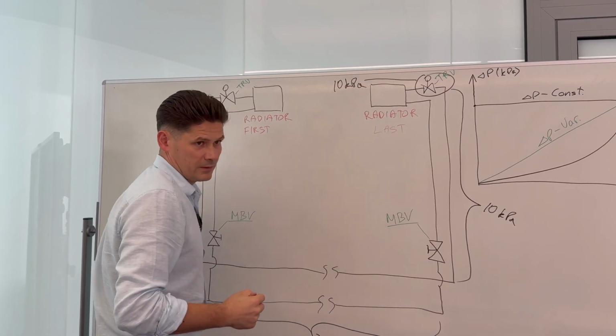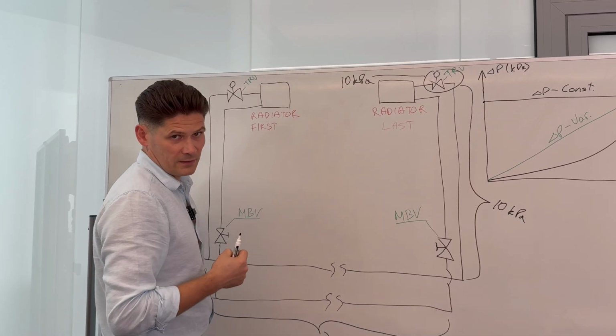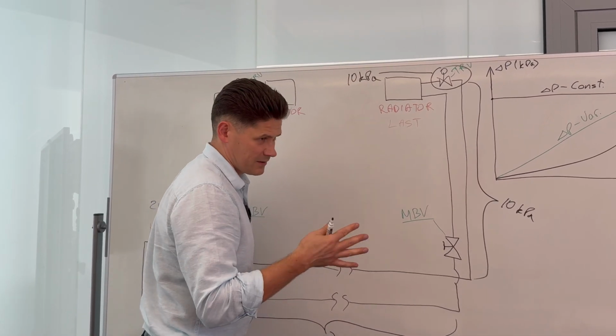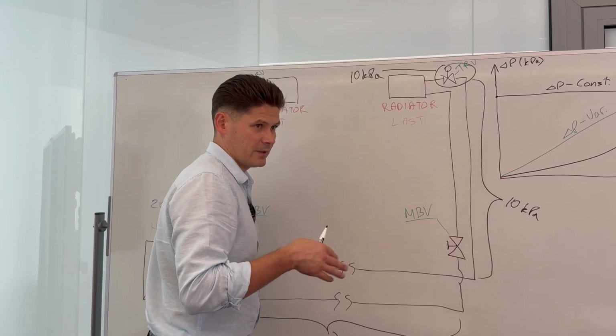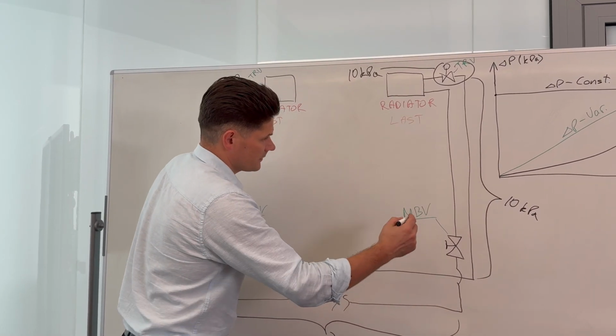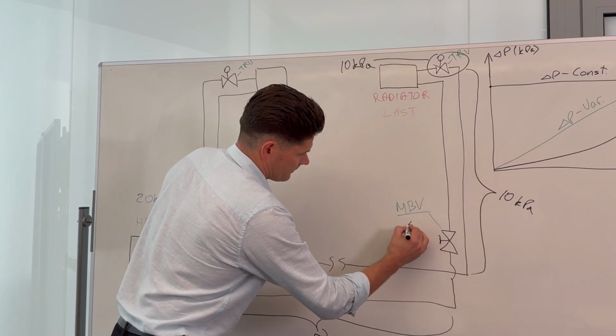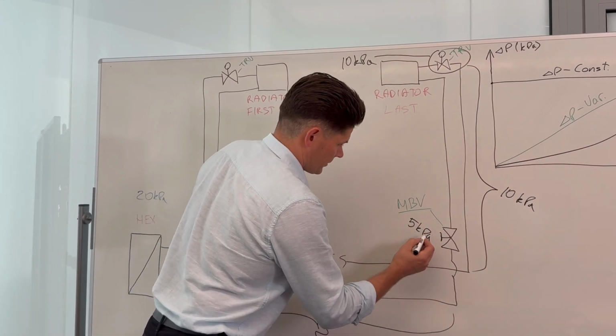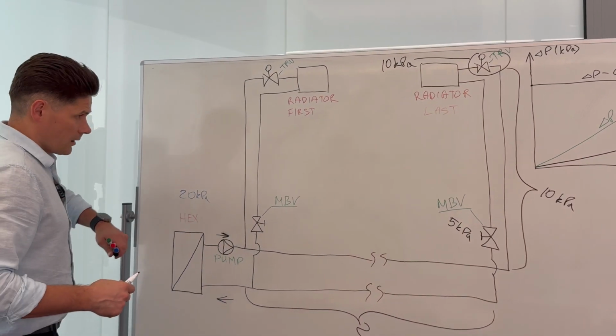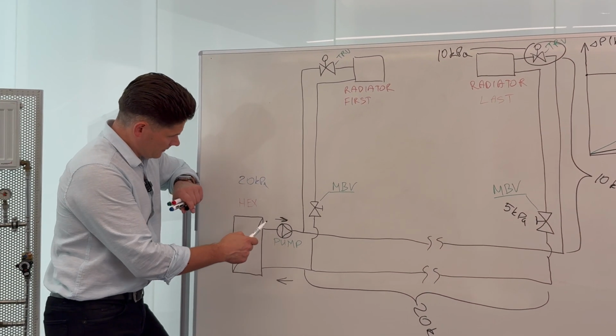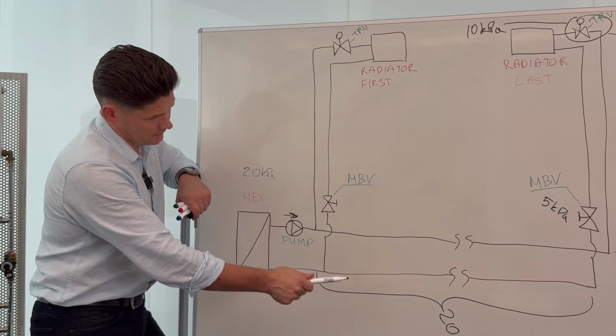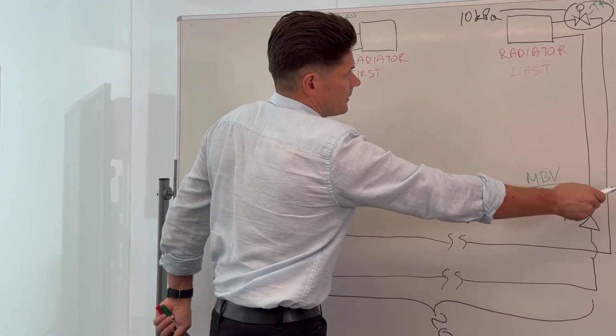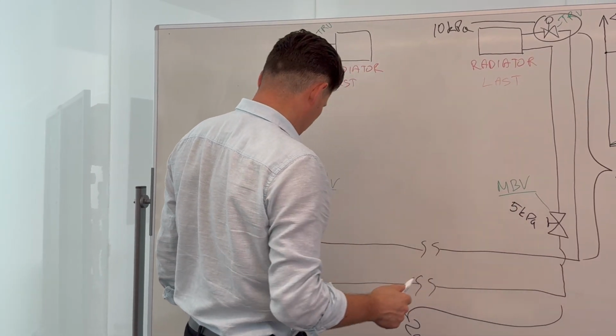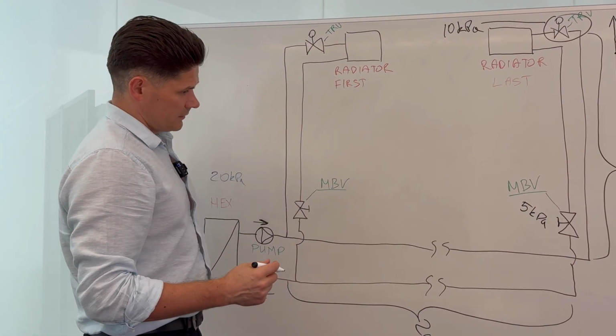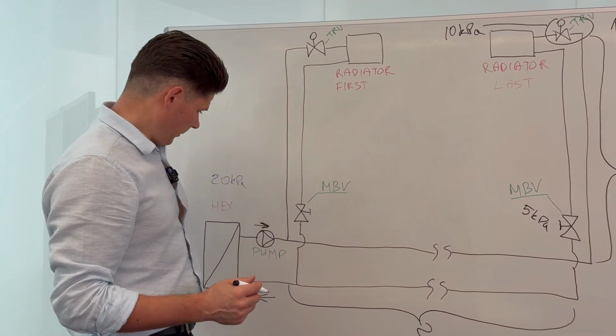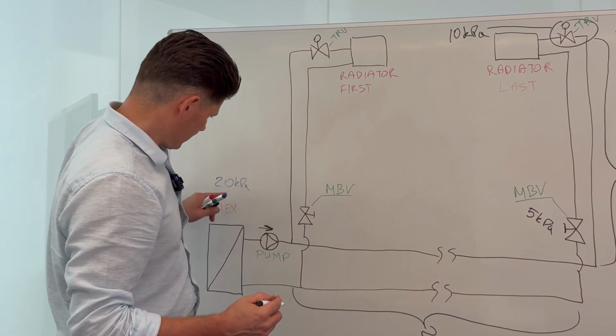For manual balancing valve, this is the last riser, so we usually take something like from 2 kilopascals. It depends from country to country, but for easy calculation, let's say here we have 5 kilopascals pressure loss. So my circulation pump then will be 20 plus 20 plus 10 plus 10 plus 5. So in total it will be 65 kilopascals, if I calculated right.